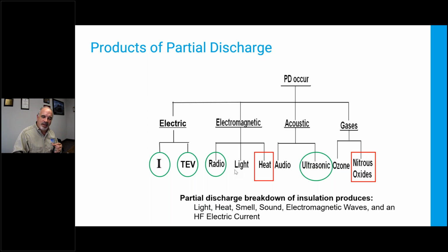The other half is nitrous oxide, right? Most of the air is nitrogen, and nitrogen forms nitrous oxide, which by itself is not harmful, but it turns into nitric acid in the presence of any humidity. So when you get that nitric acid, that is going to eat through your insulation. And so if you think about surface discharge being the fastest moving, it suffers from the heat and it suffers from the nitric acid. Internal discharge just suffers from the heat, doesn't get nitric acid because it's not in contact with air, and that moves a lot slower. Kind of makes sense. A lot of this is common sense.